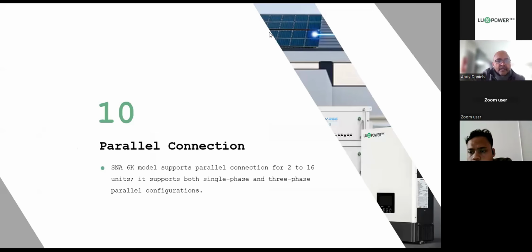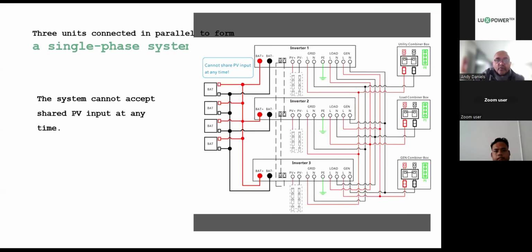All right, and then parallel connection. The SNA 6 supports parallel connection from 2 up to 16. Obviously, 1 is 1, but paralleling, you'll go from 2. You can do a maximum of 16 units in parallel, and it supports both single-phase and 3-phase parallel configuration. And as I mentioned earlier, the 3-phase parallel configurations can be unbalanced, which means you can have 1 machine on phase 1, 3 machines on phase 2, and 1 on phase 3. We've got many applications like that. They work well, and our engineers have done a lot of work on maximizing the logic for doing installations like this.